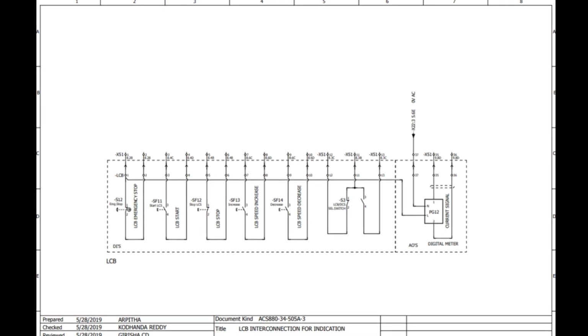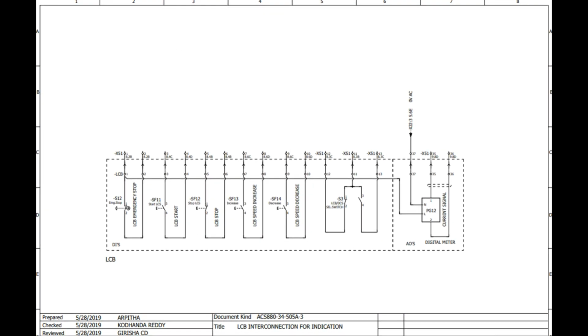Next we'll come to the different connections. The first thing you can see here is the LCB connection, that is the LCS connection. You have heard me saying X51 channel number 1, 2, 3, 4 and all those things. So this is the X51 slot, and the first channel and the second channel are for LCB emergency stop, the emergency push button signal, you can see the symbol. Then channel numbers 3 and 4 are for LCB start, that is the push button. 5 and 6 are for LCB stop, again the push button. Next, 7 and 8 are for speed increase, 9 and 10 for speed decrease.